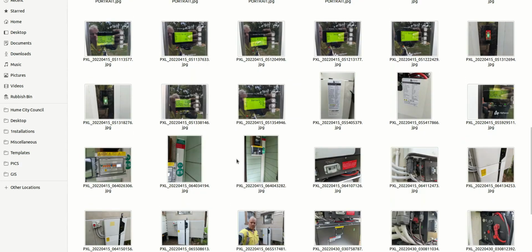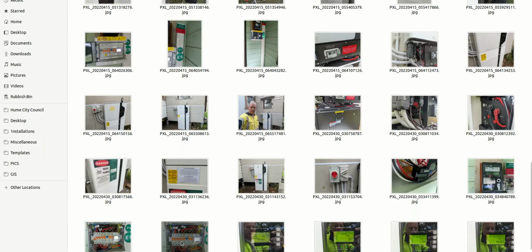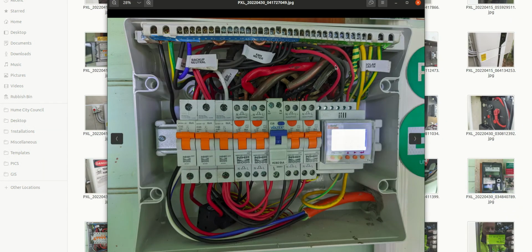Turns out when I went back, yeah, sure, I had to fix that. Yeah, sure, where is it? Here it is. As you can see, went back out there, put the other 2 wires in, very, very small terminals. And I didn't want to put an extra circuit breaker in there. It was a tight squeeze just for running some voltage wires to the kilowatt hour meter. So I actually ran 4 mil in there. And they all had to go back to the 25 amp circuit breaker. It was just too compact in here.